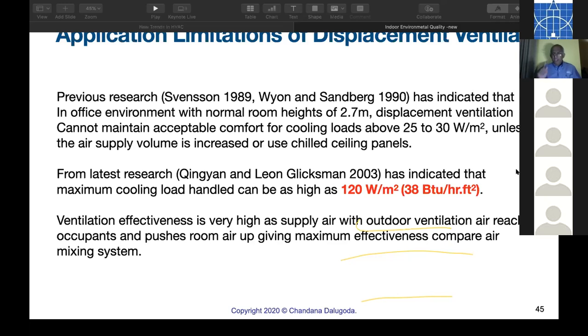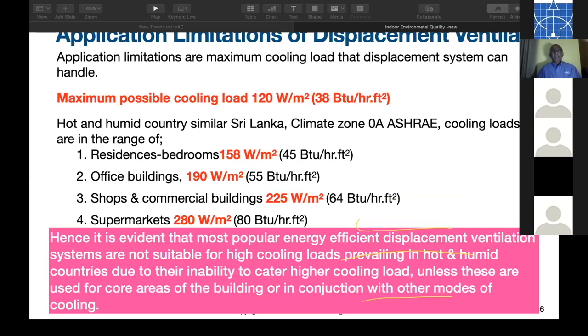Can we use this in Sri Lanka? That we'll have to see. Application limitations: the maximum possible cooling load is 120 watts per square meter. Now, Sri Lanka is a hot and humid country. The climate zone is 0A from ASHRAE. Now, for our cooling loads, we will take a residence bedroom.